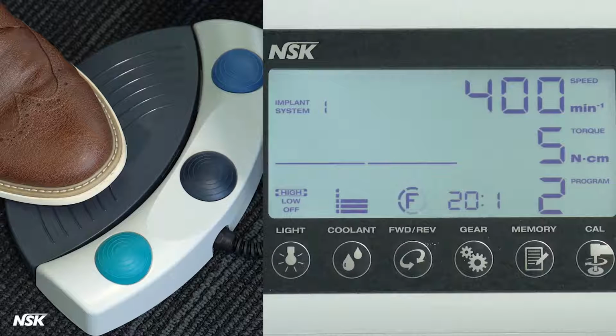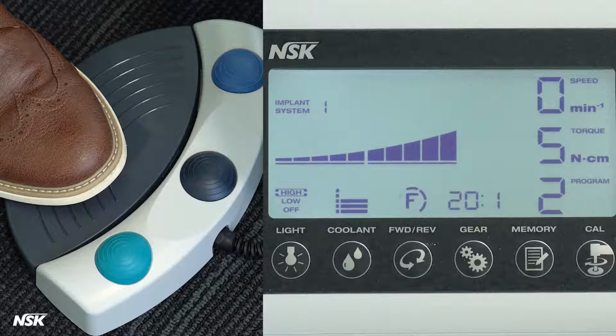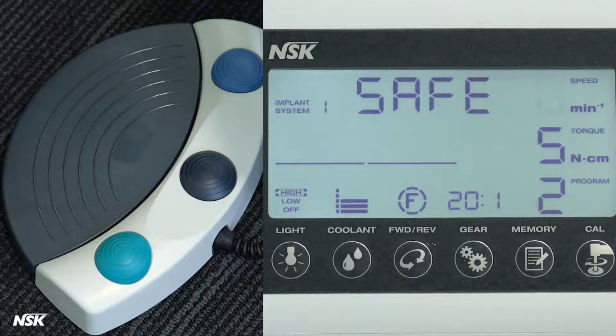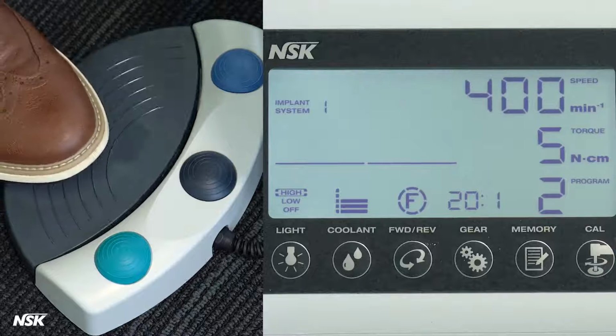micromotor and the pump. If at some point in a procedure, a drill becomes stuck in the bone and the torque exceeds the set value in the program, the error message "Safe" will appear on the panel. You will hear a beep and the device will stop. Tap on the speed pedal to clear the error.